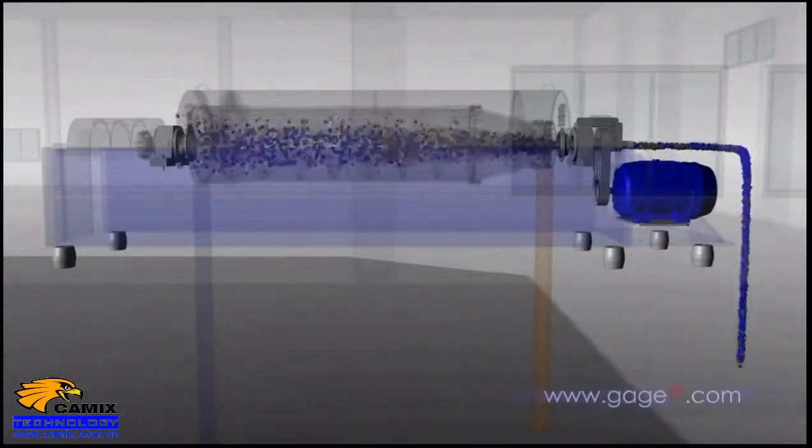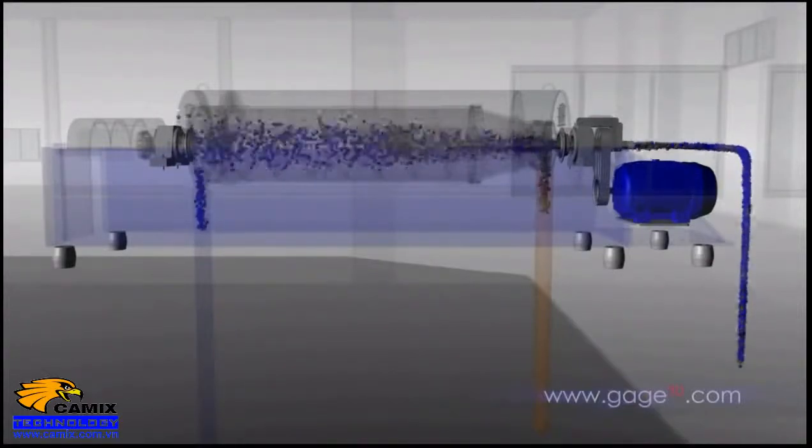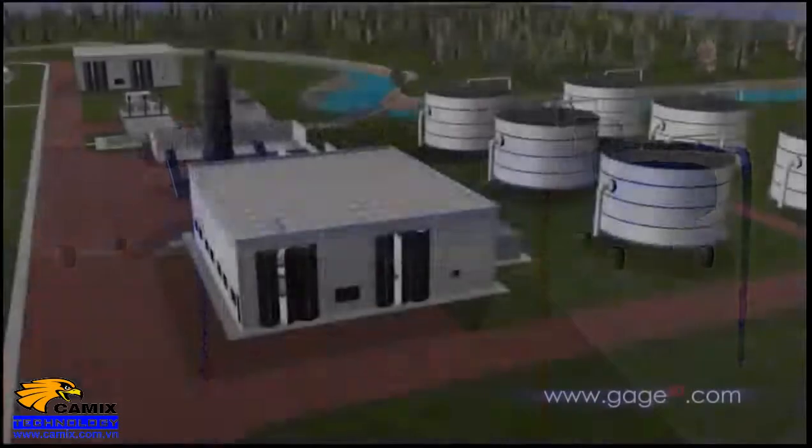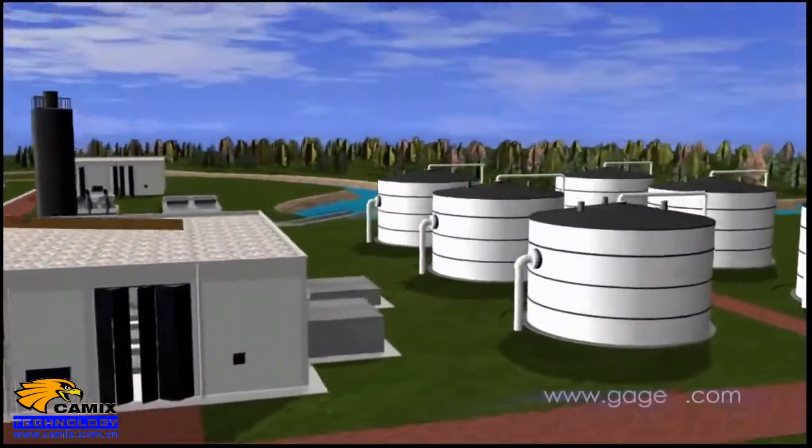The first step shown here is a centrifuge, which uses a spinning action to separate the water from the solids. The water that is removed goes back to the beginning of the treatment process, the headworks.